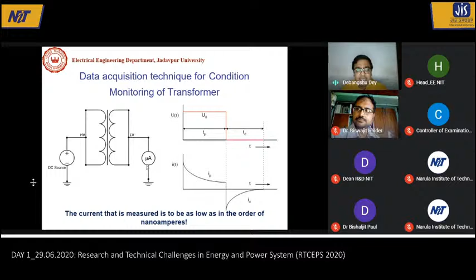So the problem is we have very low level data acquisition. That means if we are trying to record the current, it could be of the order of microamperes, or even nanoamperes if the insulation is very good. So this current will be very low, making it more susceptible to noise contamination. One important aspect of this data acquisition is that we have to denoise it properly, otherwise you cannot have reliable data.